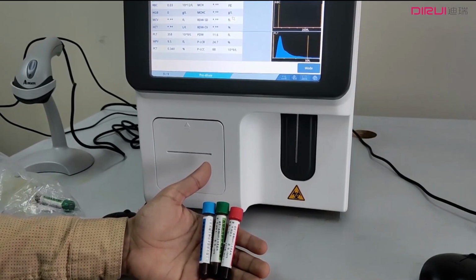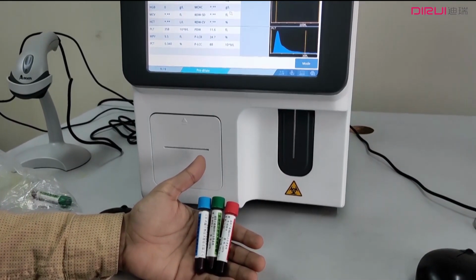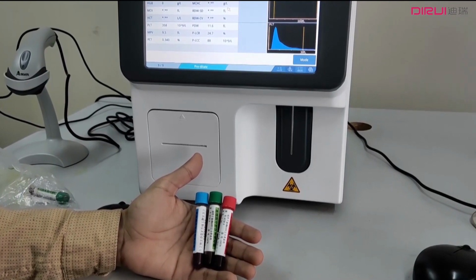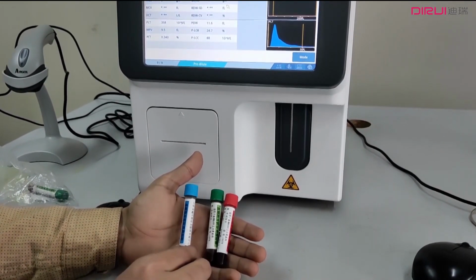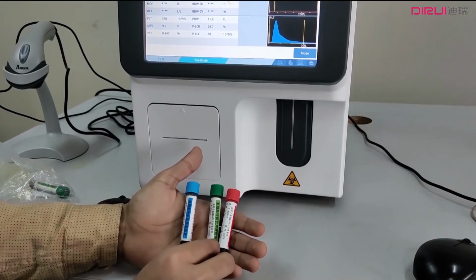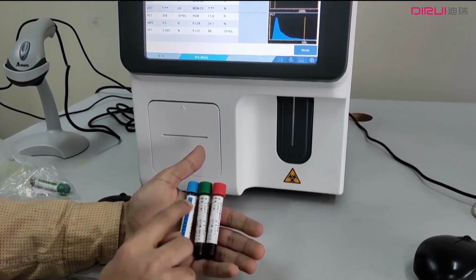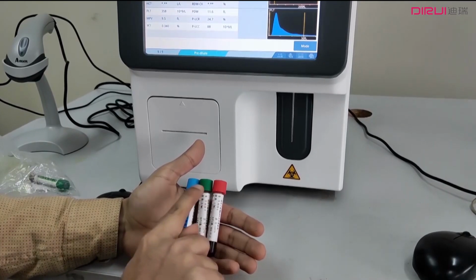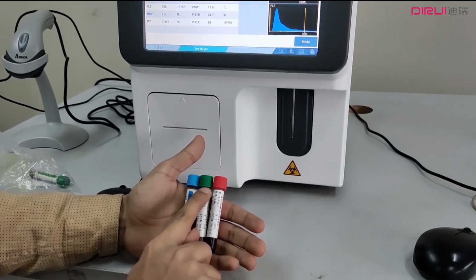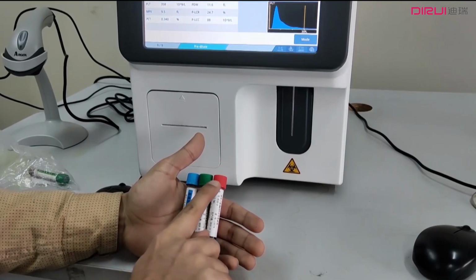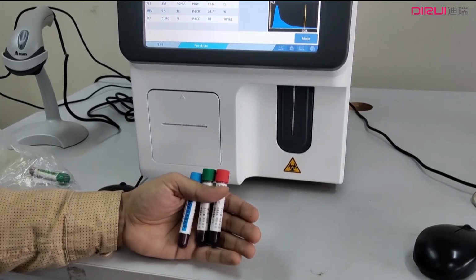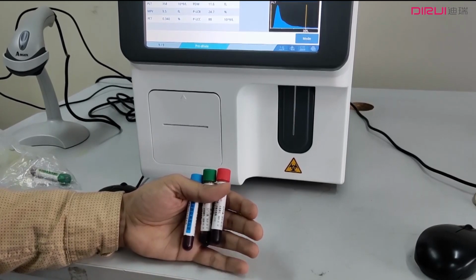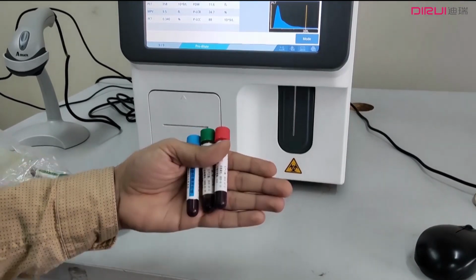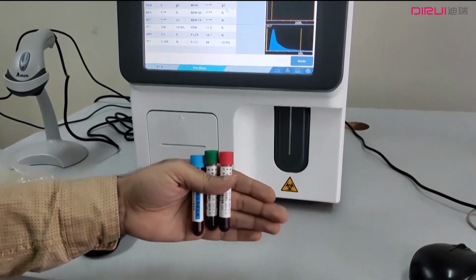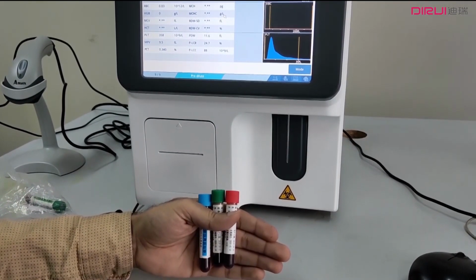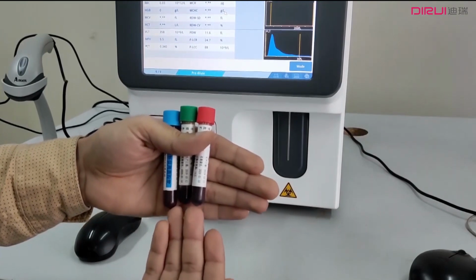After the successful calibration, it is time to do quality control. Before we conduct quality control, I want to introduce: this is low level quality control, middle level and high level. You can differentiate them from their color: blue, green and red, low, middle and high. The same method you did for calibration, you need to shake these QC slowly and normally. You do not need to push it hard because it is possible you can break cells inside.